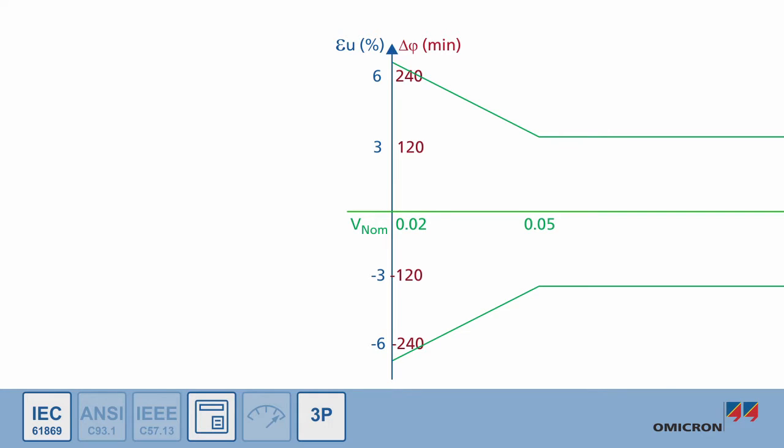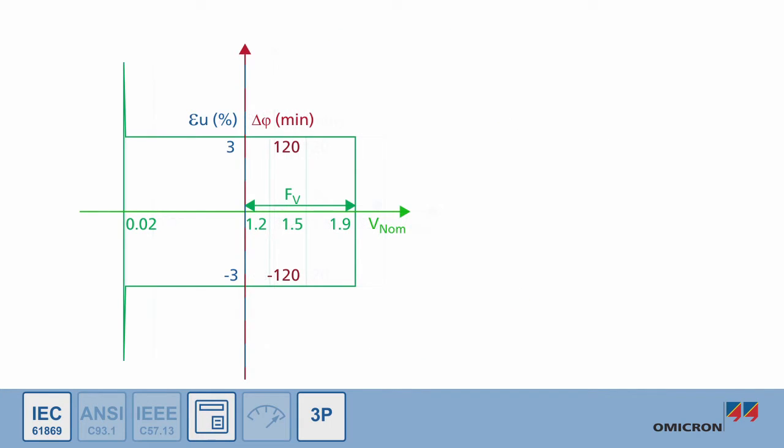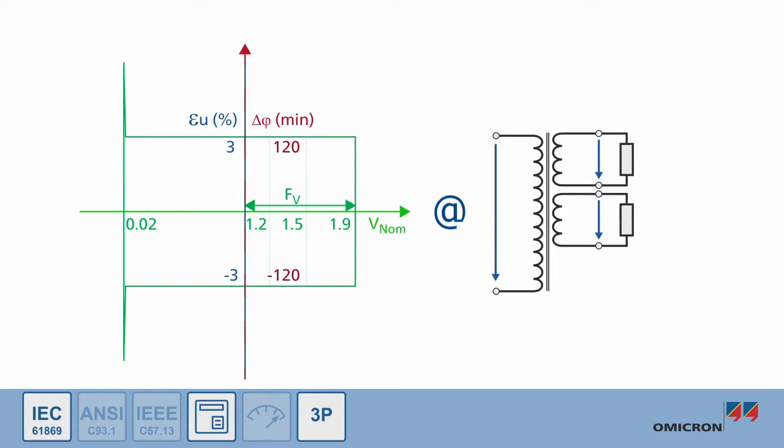At 2% of nominal voltage, the error must not exceed double of what the class limit is. These accuracy requirements must also be maintained by voltage transformers with several secondary windings when all of them are fully loaded.